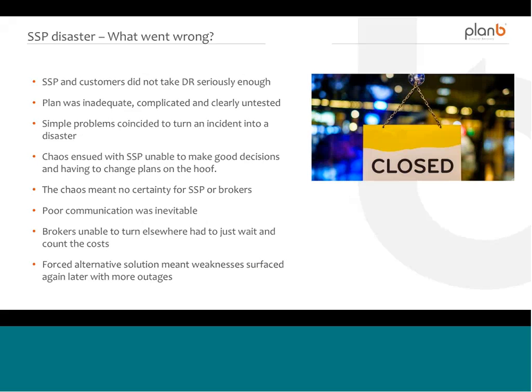It was complicated, based on taking data backups to different locations and to the same location and to different locations, and then rebuilding their systems from those backups. I suspect they never envisaged losing all their systems and having such a large amount of damage to their storage infrastructure. But the reality is that was created by such a simple thing as a break in the mains power. Their plan was clearly inadequate, complicated, and untested. Otherwise, they would have understood it was inadequate and complicated.